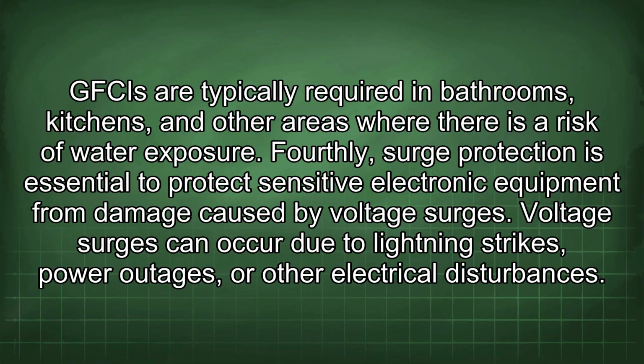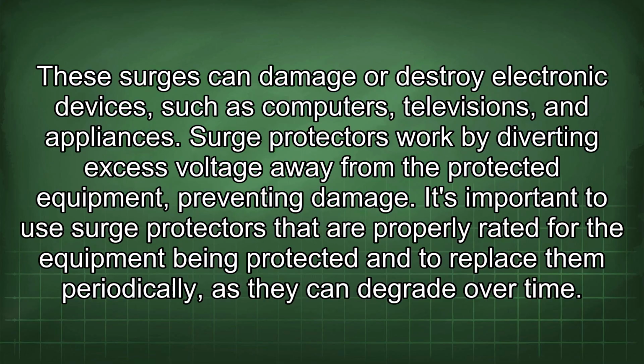Fourthly, surge protection is essential to protect sensitive electronic equipment from damage caused by voltage surges. Voltage surges can occur due to lightning strikes, power outages, or other electrical disturbances. These surges can damage or destroy electronic devices such as computers, televisions, and appliances. Surge protectors work by diverting excess voltage away from the protected equipment, preventing damage. It's important to use surge protectors that are properly rated for the equipment being protected and to replace them periodically, as they can degrade over time.